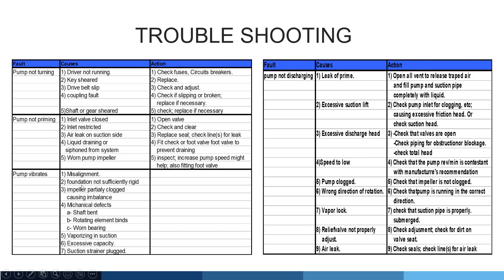Pump vibrates. Causes include: misalignment, foundations not sufficiently rigid, impeller partially clogged causing imbalance, mechanical defects, shaft bent, rotating element bent, worn bearings, vaporizing in suction, excessive capacity, and suction strainer blocked. These are the major reasons for pump vibration.